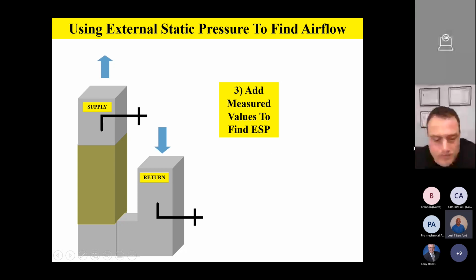So in summary, one more time, on an air handler, we're reading supply pressure right in the supply duct, and we're going to position the return static pressure probe, and we're going to point it into the airstream where it's going to be reading the maximum suck that fan is pulling against the ductwork and or filter if it happens to have the filter in there.